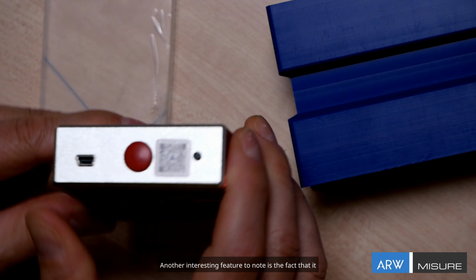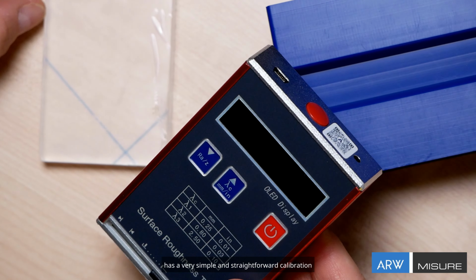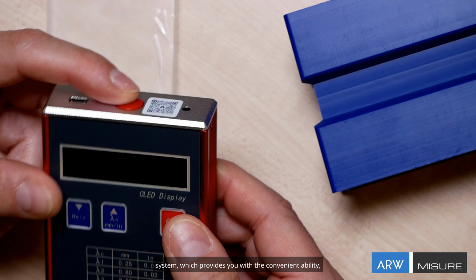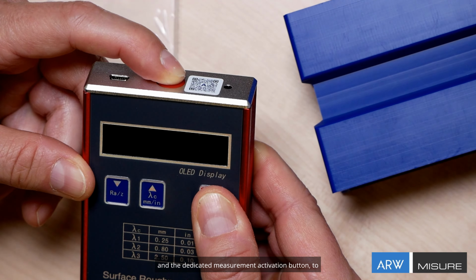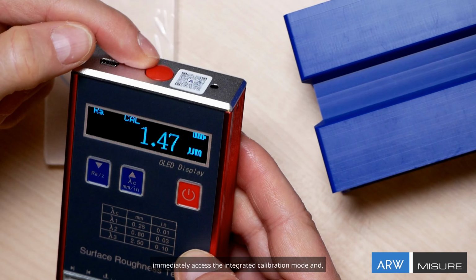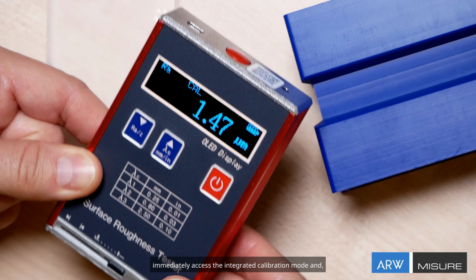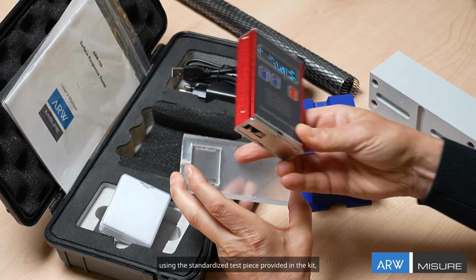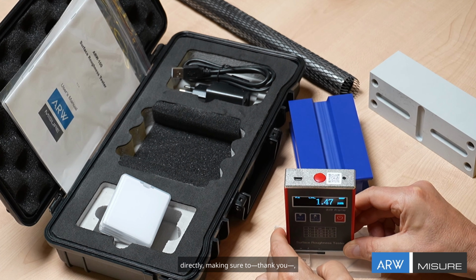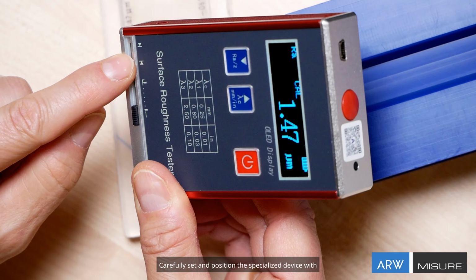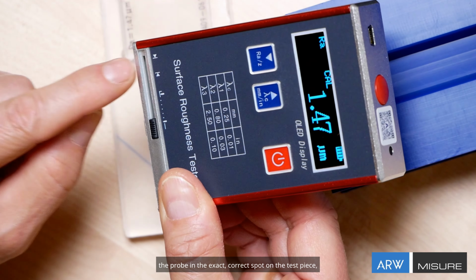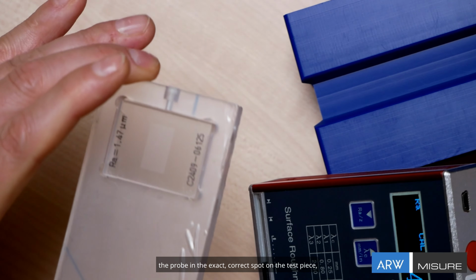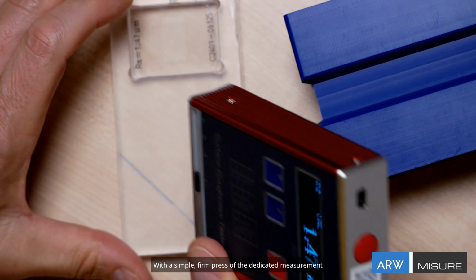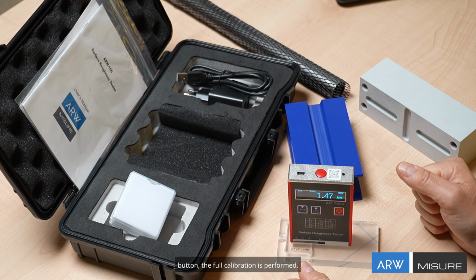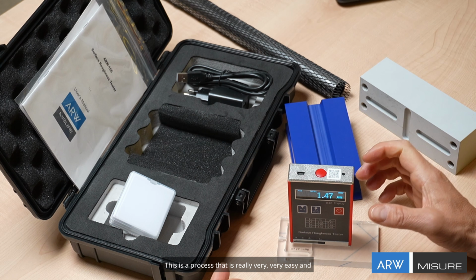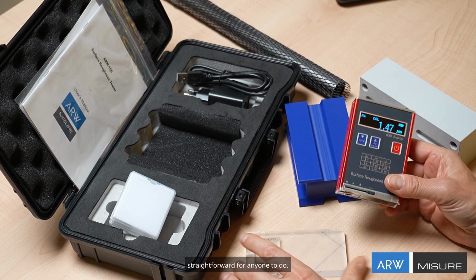Another interesting feature to note is that it has a very simple and straightforward calibration system, which gives you the convenient ability, just by pressing the power button once and the dedicated measurement activation button, to immediately access the integrated calibration mode and, using the standardized test piece provided in the kit, to execute the full calibration procedure directly, making sure to carefully set and position the device with the probe in the exact correct spot on the test piece, specifically where the area to be tested is located. With a simple firm press of the dedicated measurement button, the full calibration is performed. This is a process that is really very easy and straightforward for anyone to do.